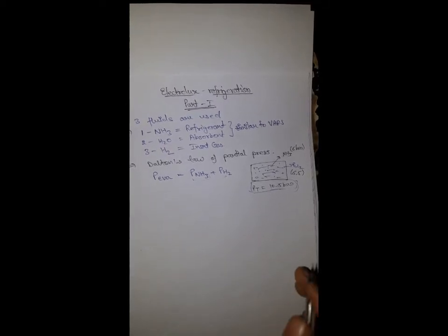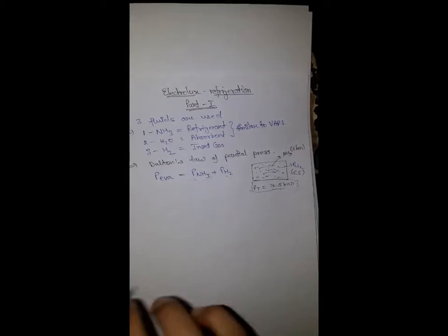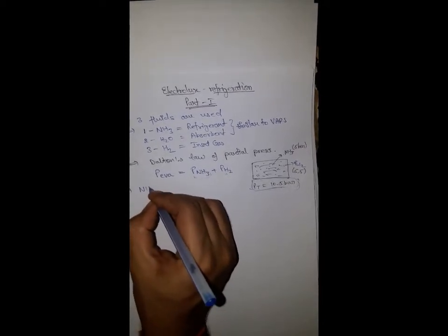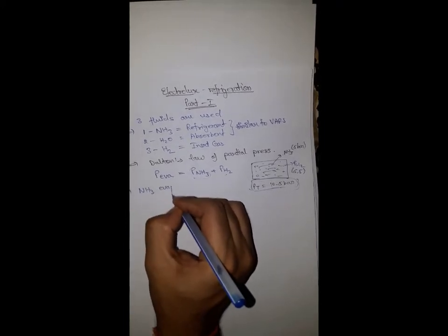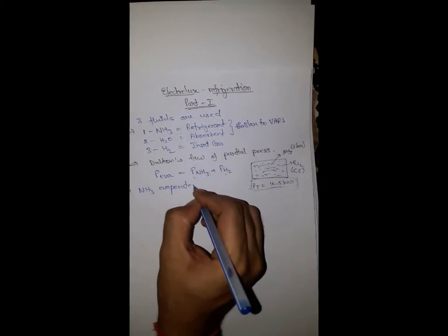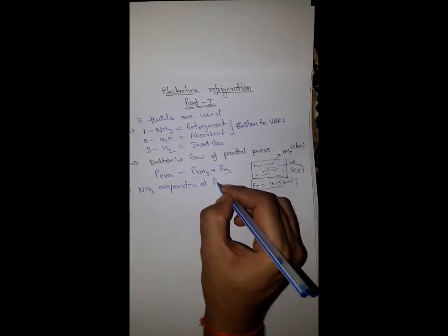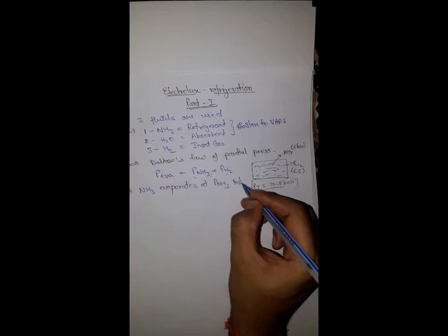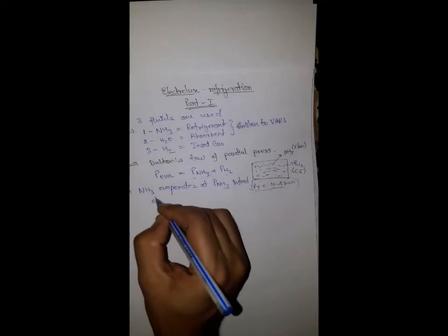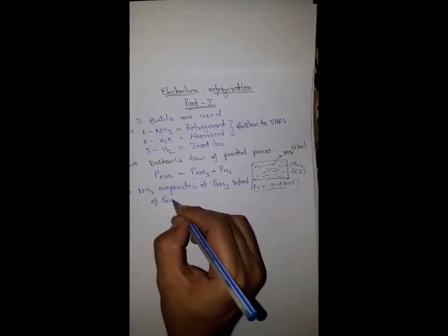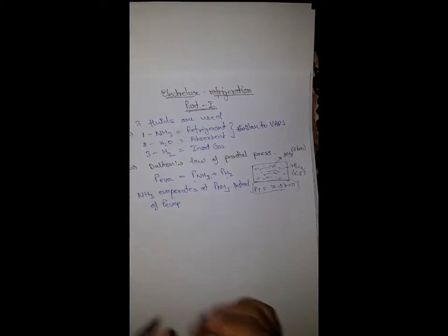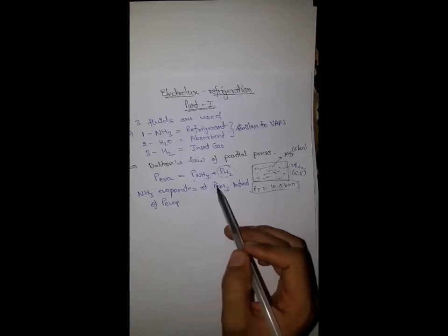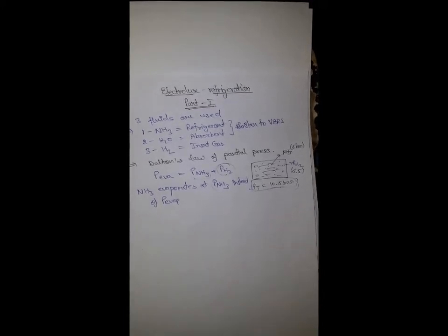So let me write it here: the need for using hydrogen is that the ammonia evaporates at P_NH3, that is the pressure of ammonia, instead of the evaporator pressure P_evaporator. Why? Because the partial pressure of hydrogen comes into play, so the pressure applied due to ammonia gets reduced.